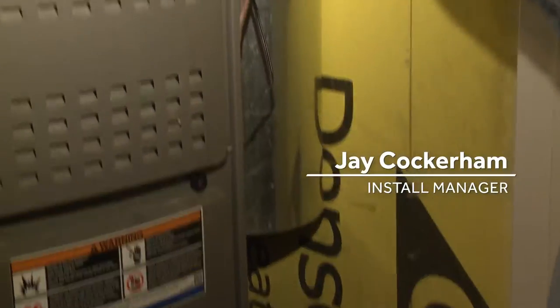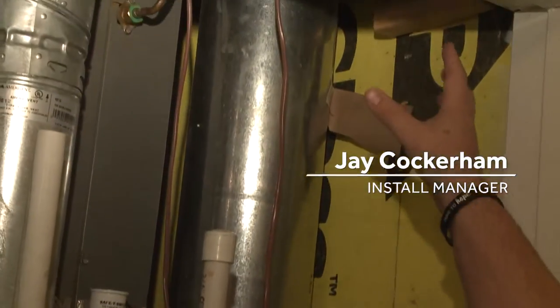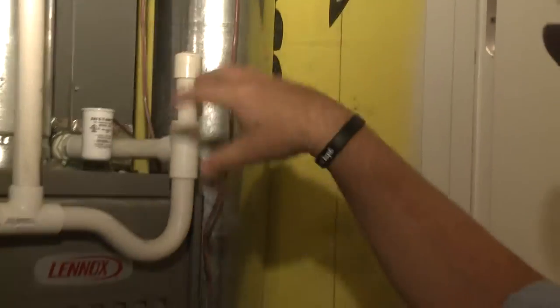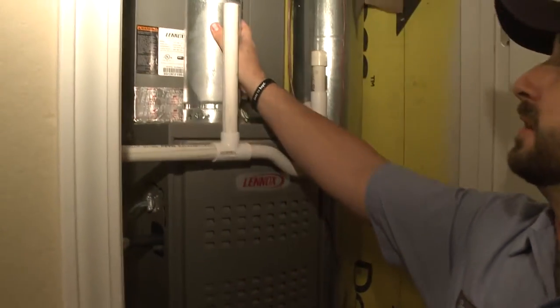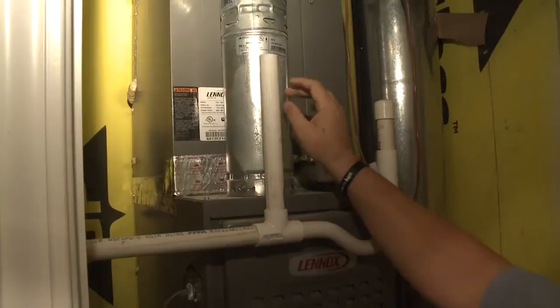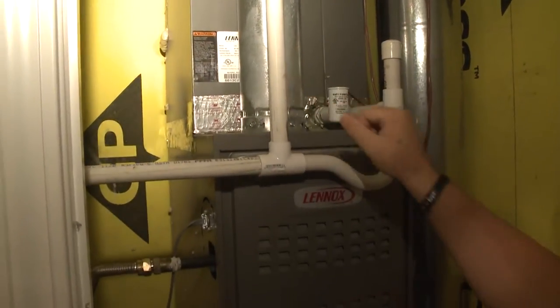This pipe down below and this pipe up above here — this is what the fire breathes from. This one feeds the fire and this one gets rid of any excess gases. Inside your closet flue pipe right here, make sure that it's in good condition and not rotting out or showing any signs of wear and tear.